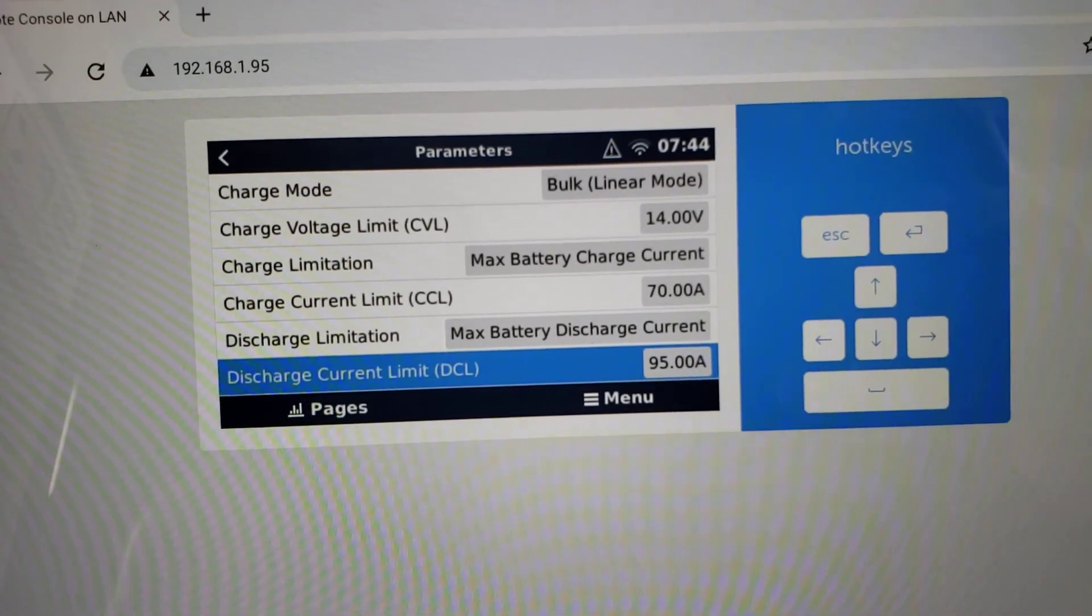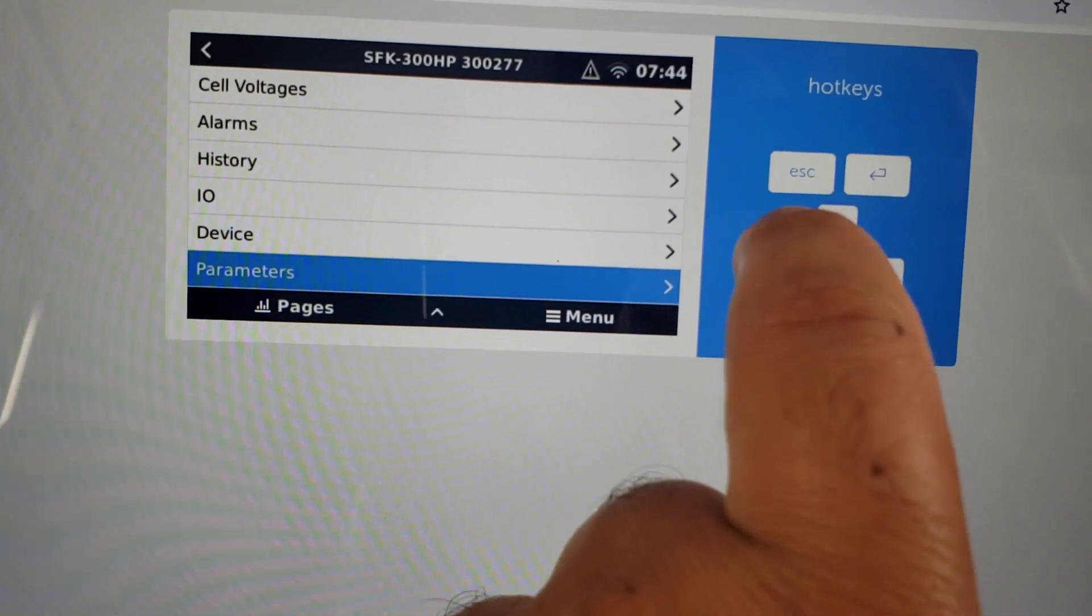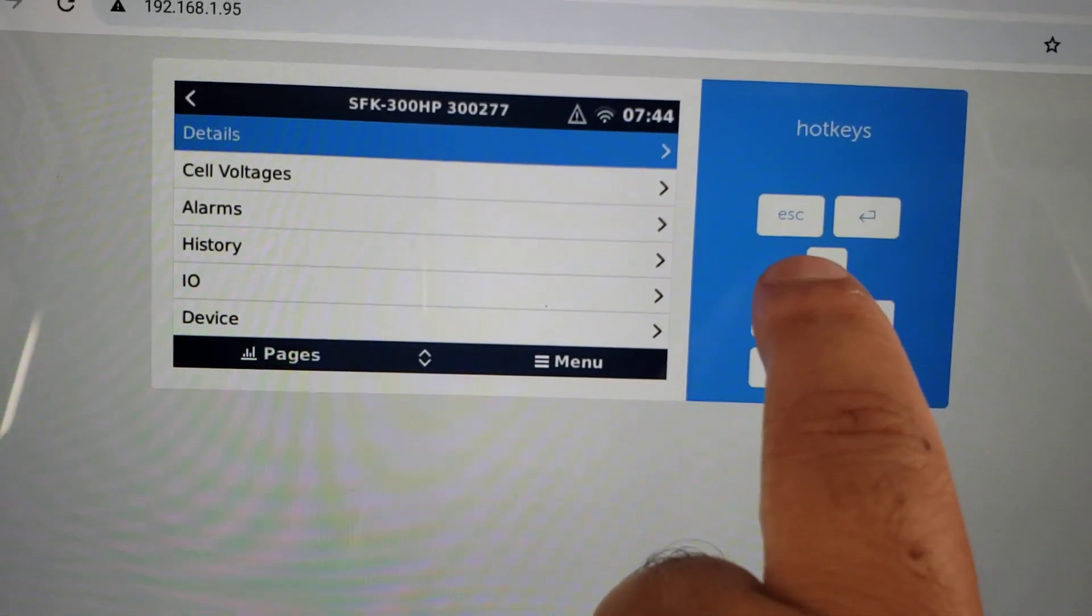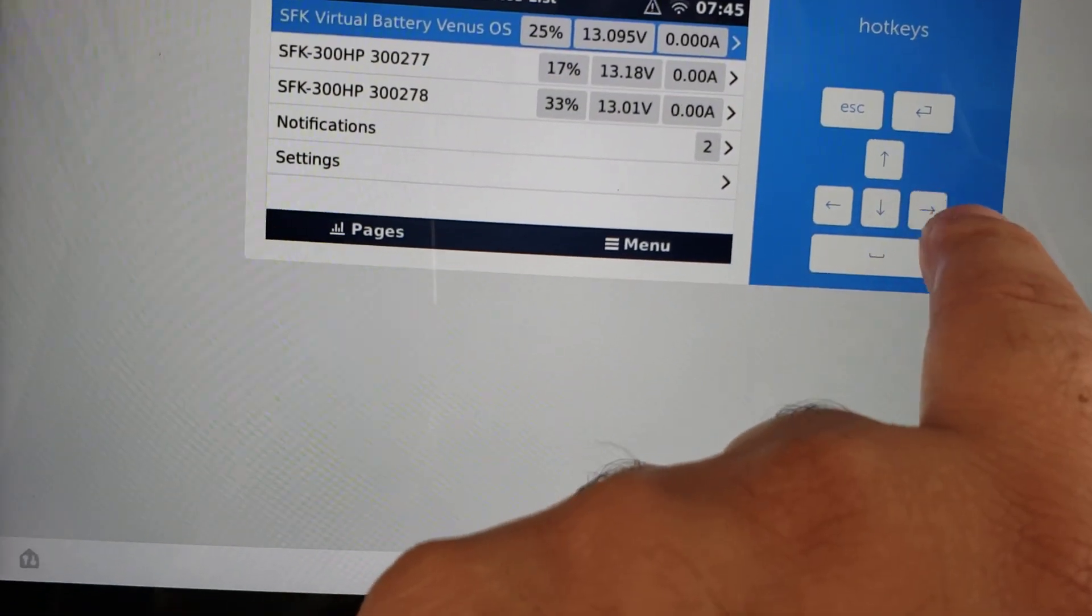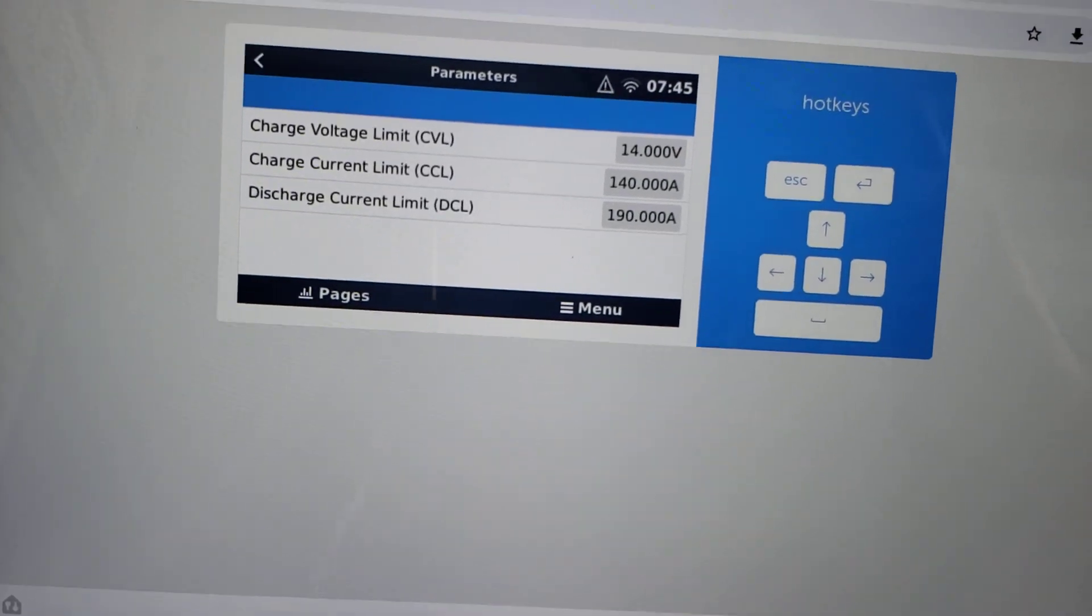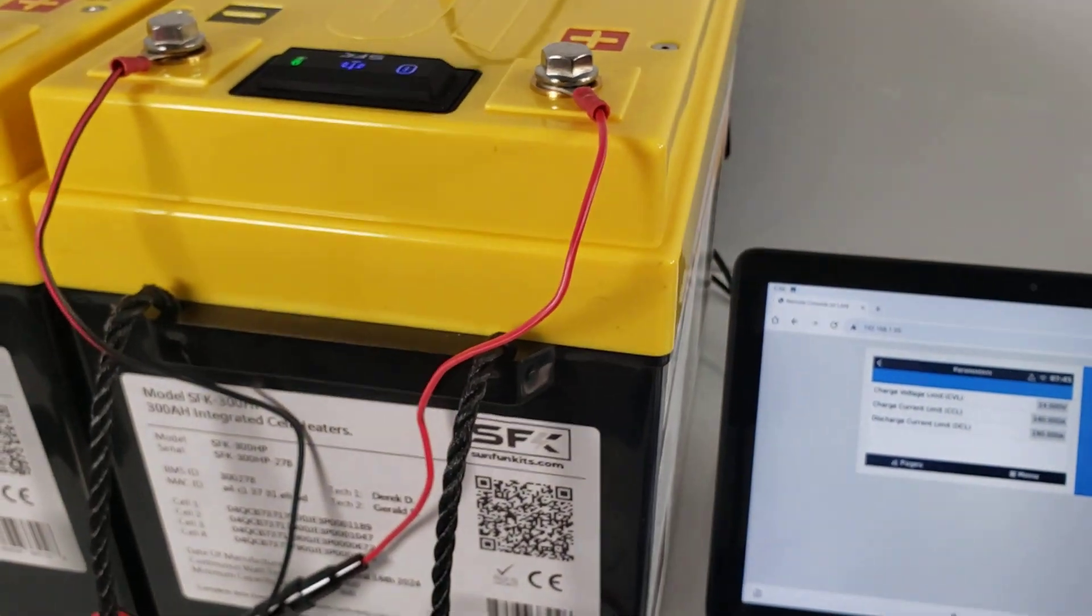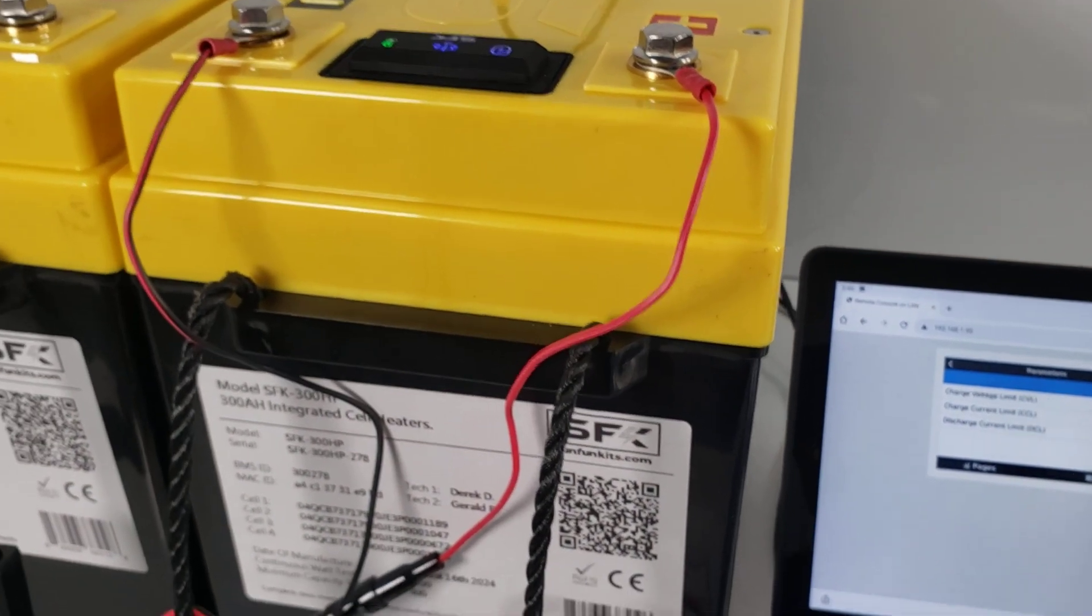And that's what we're seeing here. If we go back to the virtual battery, in the virtual battery, if we go here and in the parameters, we'll see that it essentially doubles it. So if you go with three or four, however many, I mean like I said we don't recommend more than four in parallel in one bank, but if you had four in parallel, it would basically parallel all those.